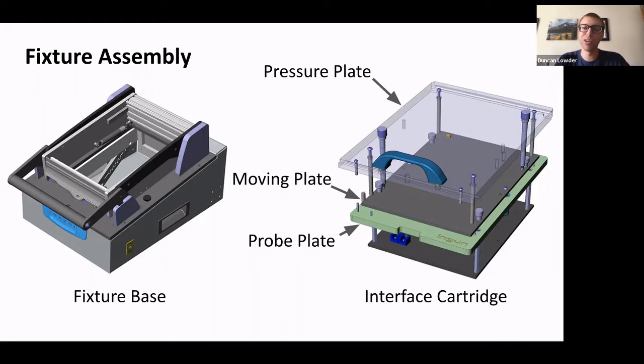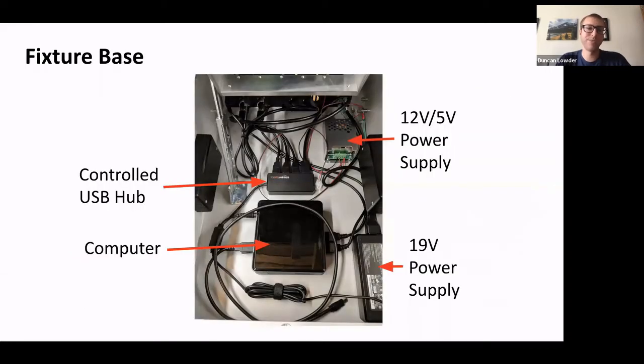The cartridge consists of three different plates that you need to customize for each circuit board. The pressure plate has pins that push down against the circuit board you're testing. The moving plate supports it from the bottom to prevent bending the device under test. The probe plate is what actually has all the pogo pins and receptacles mounted to it. Within our test fixture bases, we integrate a computer, usually an Intel NUC, as well as a USB hub, and any power supplies needed by the fixture.